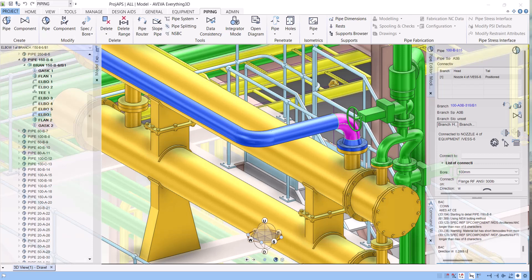There are many types of slopes in piping. In some services we give slope one is to 50, in some services we give slope one is to 200. You have to give only the slope which is available on the P&ID. When you refer to any P&ID, the slope is mentioned on the line. So here I am giving slope one is to 200.